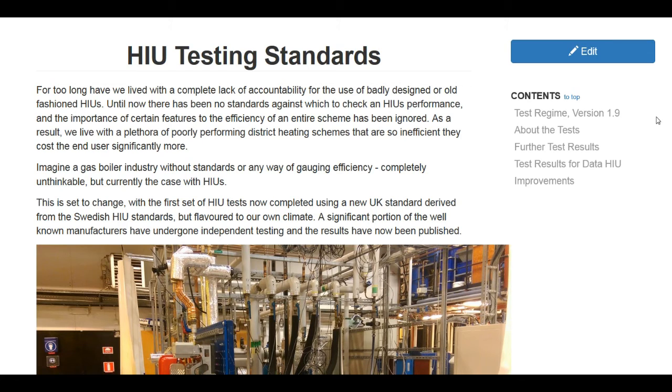Now the benefits of being able to guarantee return temperatures as low as 35, is it reduces heat losses on the pipe work, as well as significantly increasing plant room efficiency. CHP plant rooms, heat pumps, all rely on low return temperatures in order to work.